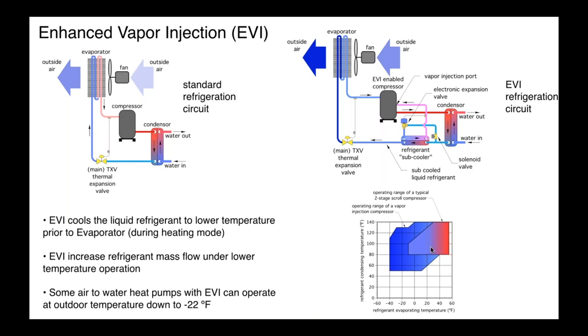And it shows you that this dark blue area represents an injection, vapor injection compressor. You can see we can actually get down in the range of minus 40 degree evaporating temperature. Now, that's not the outside air temperature. That's the temperature of the refrigerant, the coldest possible temperature of the refrigerant. But that substantially increases the lower end of the outdoor temperature range where these air source heat pumps can work. And EVI technology is not used just in air-to-water heat pumps. It's used in other types of heat pumps as well.